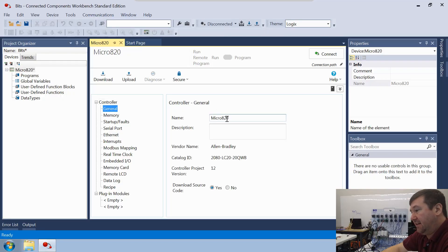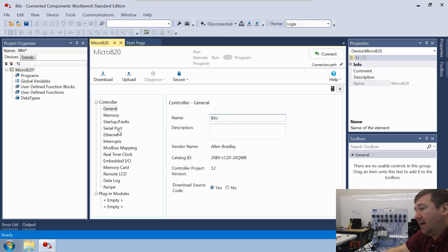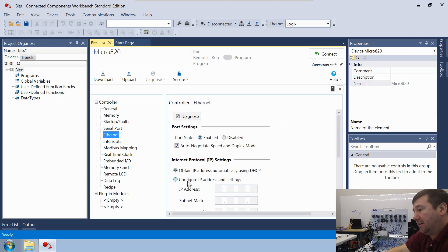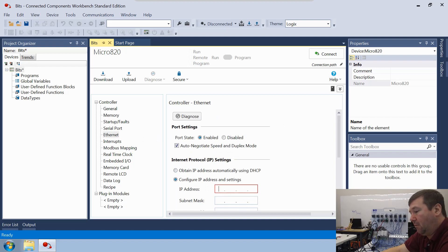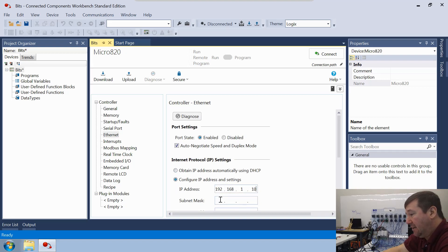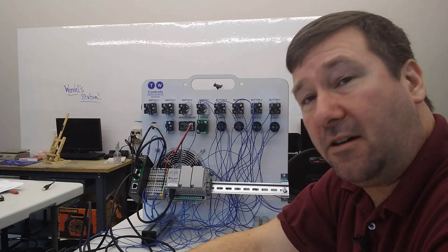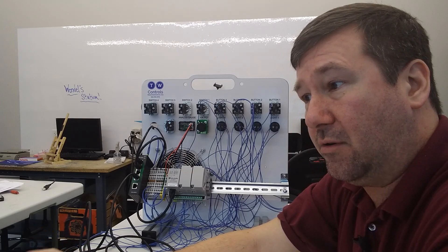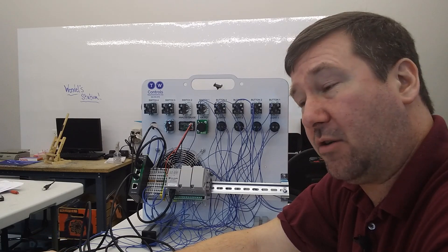Let's go ahead and give this a name beyond Micro 820 — we'll just call it BITS. We're going to configure our Ethernet and it will be our default address for our trainer, which will be 192.168.1.10, and the default subnet of 255.255.255.0 will work great. That's all the configuration we need to do in our controller, so we're ready to create a program.